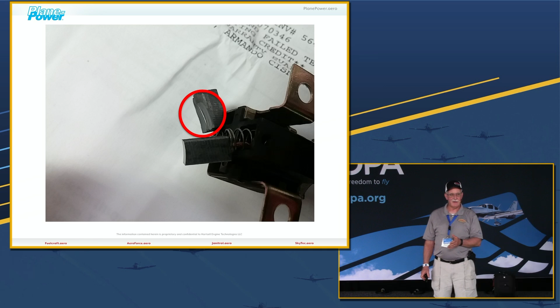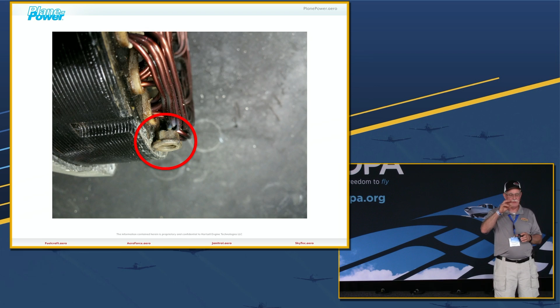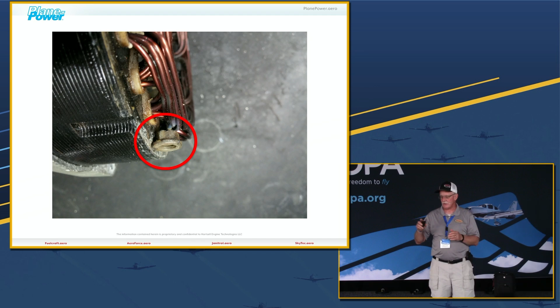Here's one that came back in. We found this nut jammed up in the stator. That nut, I call those turbine nuts, just my old way of saying it - nothing we actually use. Somehow that nut got into that side of the alternator and wore through the varnish on the outside of the stator, and you can see the result - it shorted right there where you see the smoke color at the nut itself. That shorted the stator, and the output was gone just like that, circuit breaker popped, the whole bit.